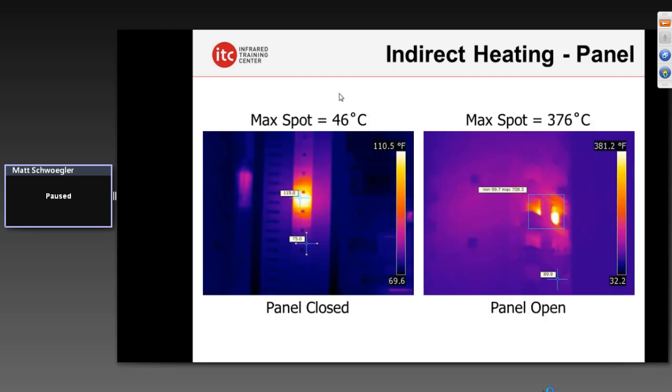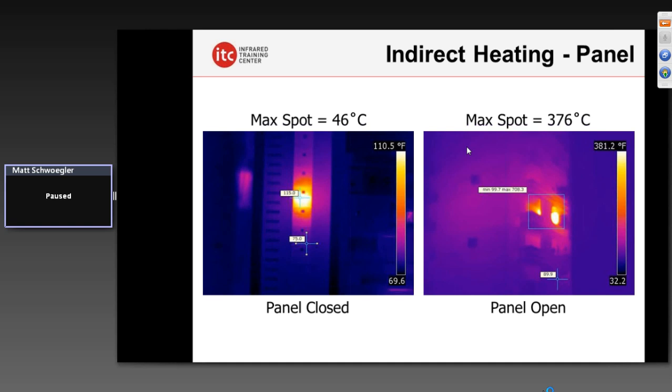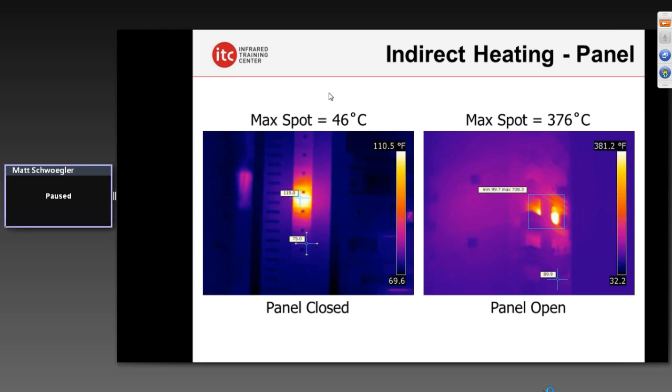Check out this example: 46 Celsius on the left — that's a 115-degree problem on top of that breaker. On the right, over 700 degrees. We need that direct line of sight. It is a myth that we can see through panels. We need to have that direct line of sight. If you're doing that, of course, safety becomes absolutely paramount — and you only do this if you're qualified.